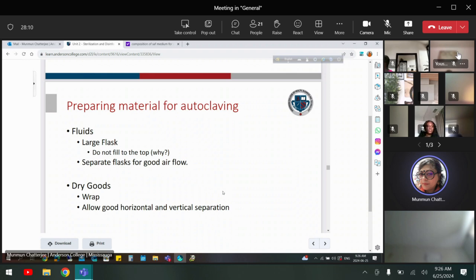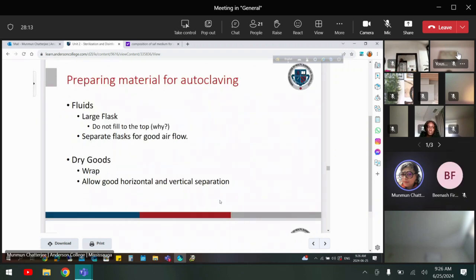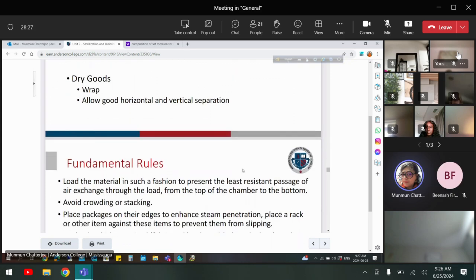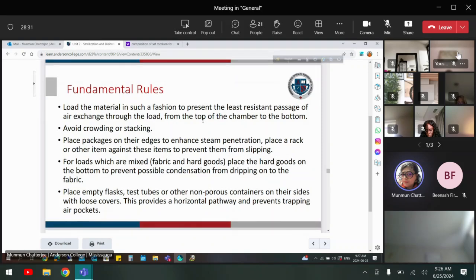Dry goods, you can wrap with muslin because it has good steam penetration and can stay sterile. Allow good horizontal and vertical separation. Keep them horizontal, and otherwise try to do it in the vertical position. Fundamental rule: load material in such a fashion as to present the least resistance to the passage of air exchange through the whole load, so that air can move freely everywhere, because of the principle of steam under pressure. If you crowd or stack one over another, the steam carried with high pressure is not going to penetrate.